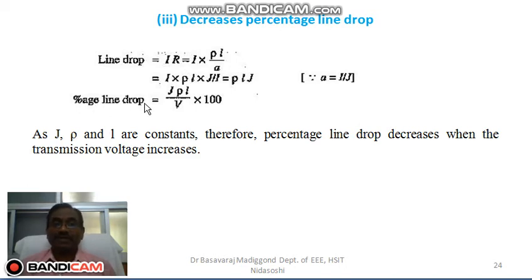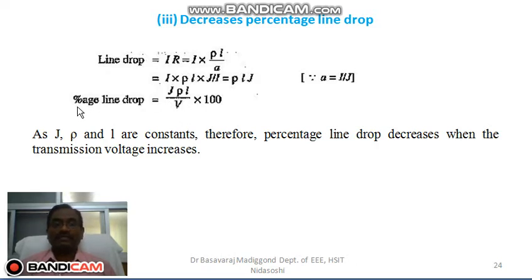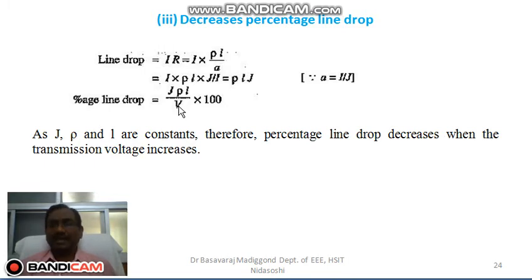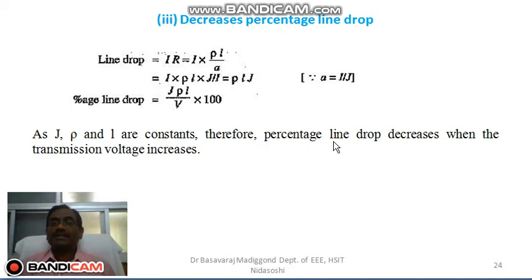This is the line drop. When we take the percentage of line drop, we divide by the transmission line voltage V. So the percentage of line drop equals jρl/V × 100, where J is current density, ρ is the specific resistance of the conductor, l is the length of the transmission line, and V is the transmission line voltage.